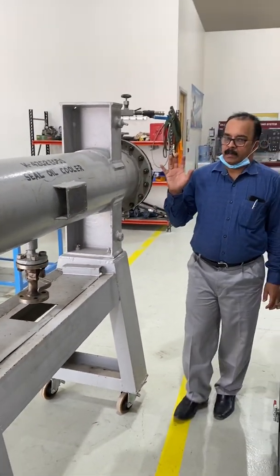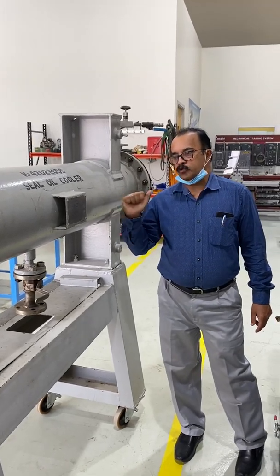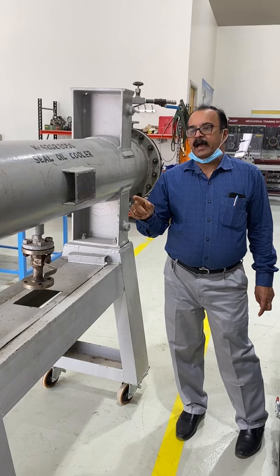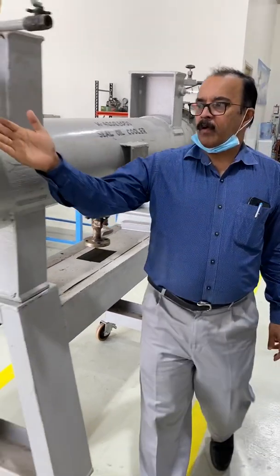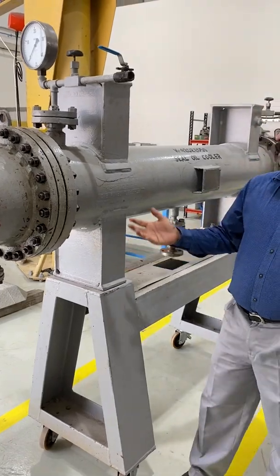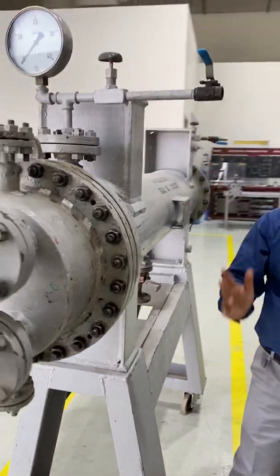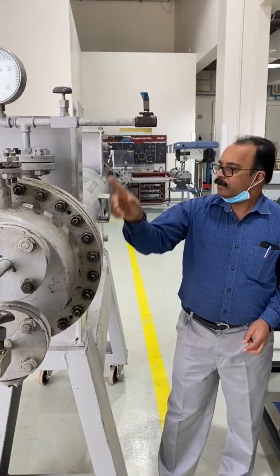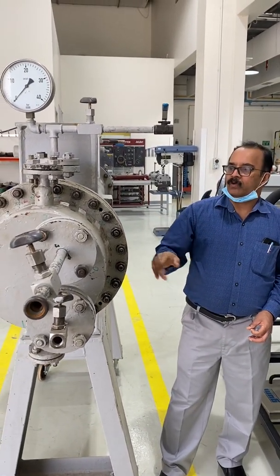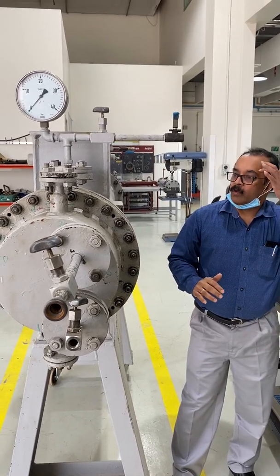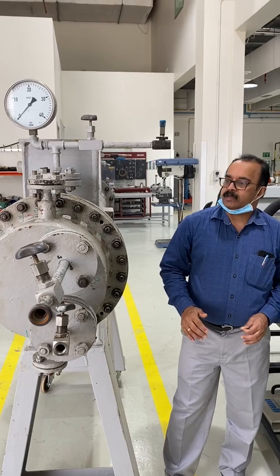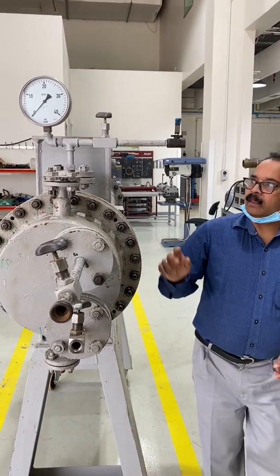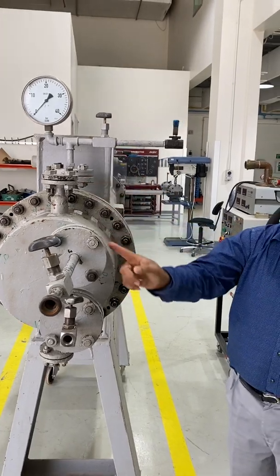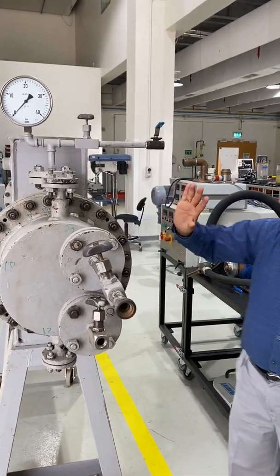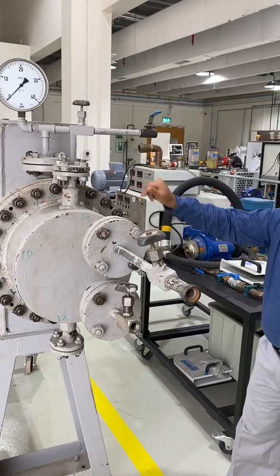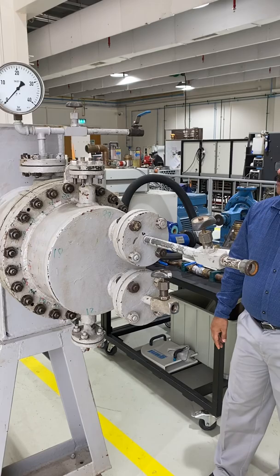So the main things are cleaning of the shell side and tube bundle and replacement of the gaskets. When you assemble, there are a lot of bolts, maybe 20 to 30; in a big one, maybe 500 or 600 bolts. The tightening of the bolts is very important. There is a sequence and a formula for tightening the bolts, otherwise it will start leaking. So according to the correct method, you must tighten with a torque wrench, otherwise it will start leaking again. Each flange must also have gaskets, and the bolts tightened according to the rules. There is a standard format for tightening the flanges. That is about the heat exchanger.